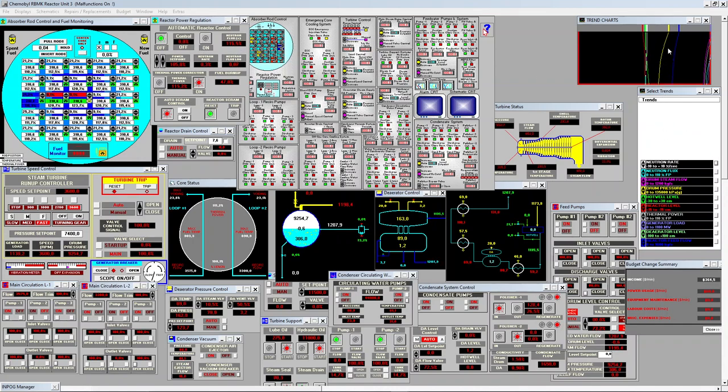You see the drum pressure, it's increasing, kind of following an exponential shape. The reactor is starting to decrease the level, so probably I will start one feed pump more to keep the reactor with a good level of water. Once it lights on, we'll open the inlet valve. On. Okay, so discharge valve, sorry, on. Okay, that's good. Now the reactor should go back to normal level. I will also start the third condensate pump in case the feed water pumps run dry.